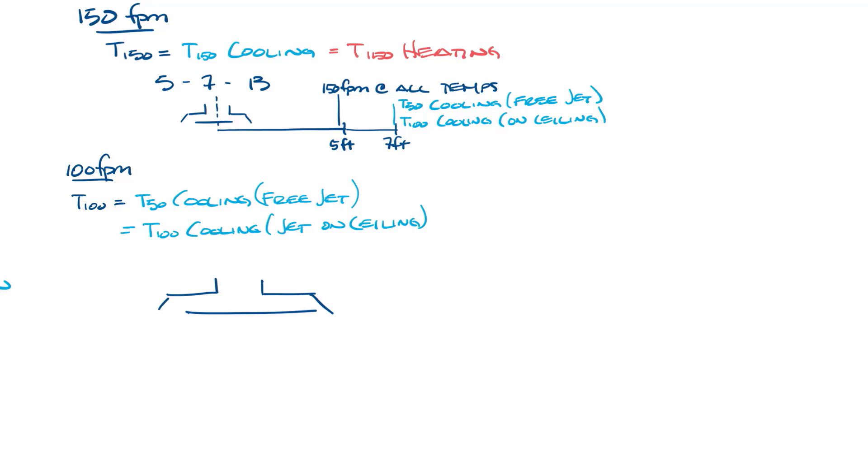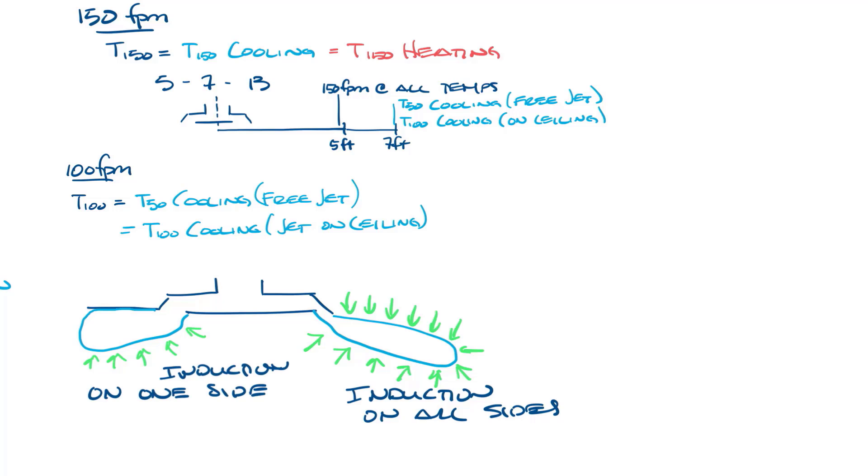The difference in throw for a free jet versus a jet moving along a surface like a ceiling is that the free jet can induce air on both sides, but a jet on the ceiling can only induce air on one side. Induction is when room air is mixed into the supply air stream. Induction of room air slows the jet down and shortens the throw.